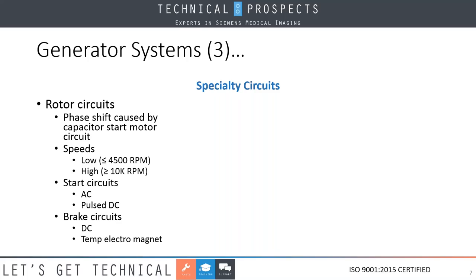Basically, this uses a very common circuit known as a cap start motor circuit with the phase shift caused by the capacitor in there. Oh, the old Eli the Iceman from your days of basic electronics. Our rotating anode generally has two speeds. Low is less than 4,500 RPM, and high speed anodes are somewhere around 10,000 RPM or higher. We have our start circuit, which can be AC, back in the simple days with the cap start, or we can now use pulse DC when we use inverter circuits today. Braking circuits, however, that are associated with the rotor are strictly a DC circuit where we apply a high DC voltage across the X-ray tube using the stator windings. And as the commutators come in, this forms a temporary electromagnet, allowing our X-ray tube to come from the high-speed rotor almost down to a complete stop.